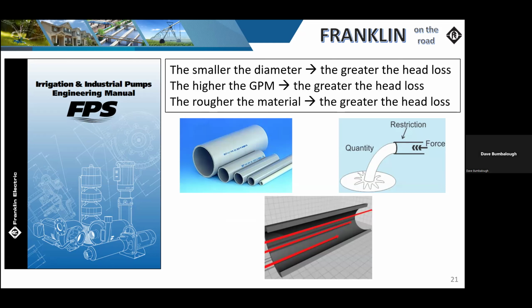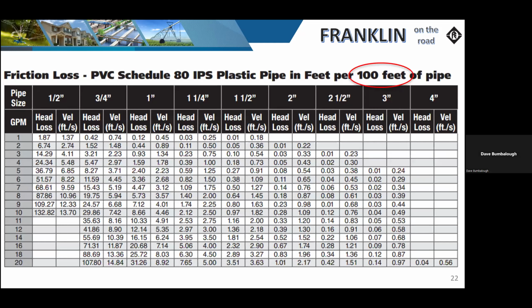But I understand the difference between them is the weight that it can support, the pressure that it can support. So you've got to pay particular attention to what pipe you're putting in there and the material of construction, so that you don't end up damaging the pipe, or getting into a situation where the product falls off the pipe because of the weight, or sometimes a run-on situation where temperature may affect the PVCs and cause them to do a ballooning action. That's a totally different subject, and I don't have anything to show you representing that at this point in time. So just keep that in the back of your mind when you're using PVC materials.